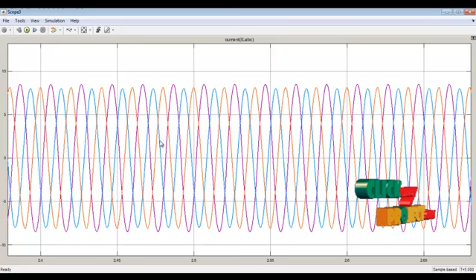So this one is the voltage at VPCC. It will be approximately 145 volts. This will be across the load. This one is the current at the load. It will be approximately 8.5 amps, and it will be constant throughout all 5 seconds. Here we analyze the total harmonic distortion at the VPCC voltage. I take the VPCC voltage, take the second phase, and by using the THD analysis we get 0.35% overall.